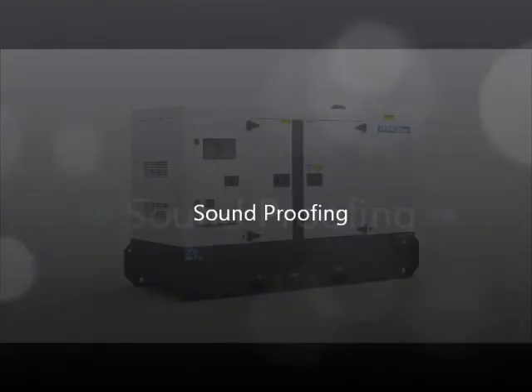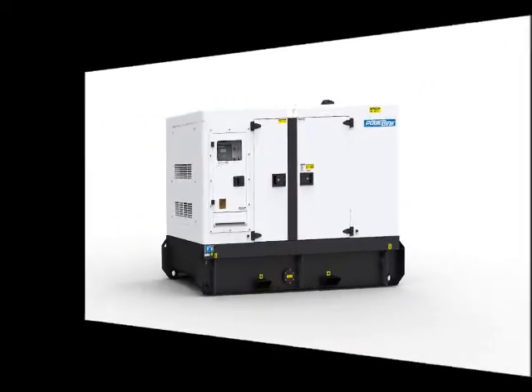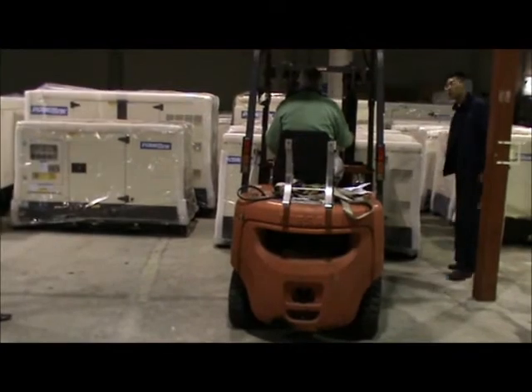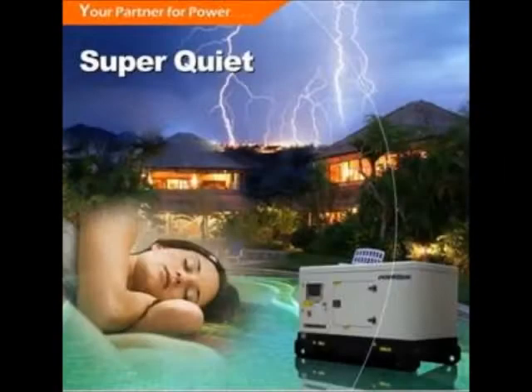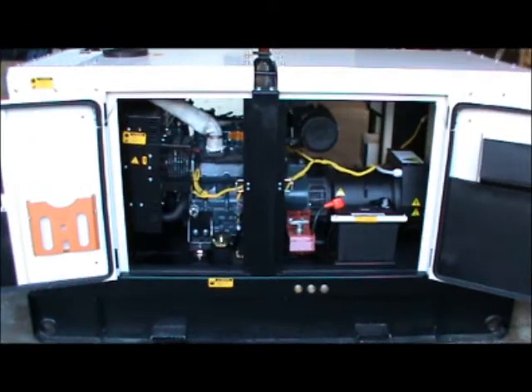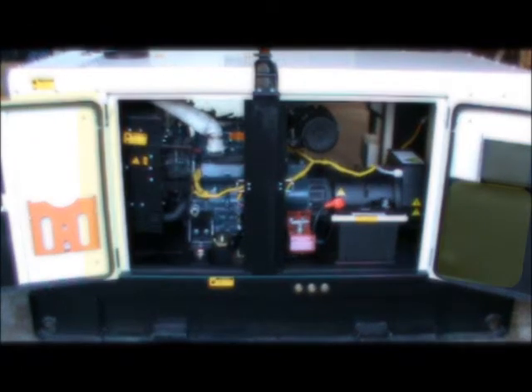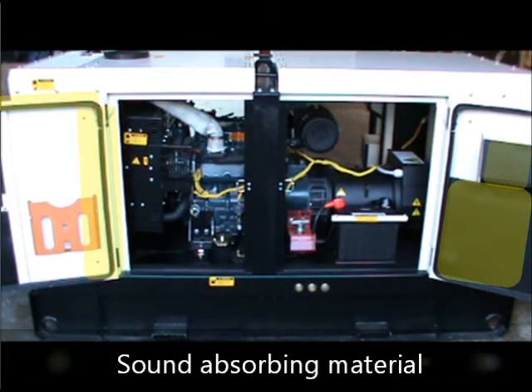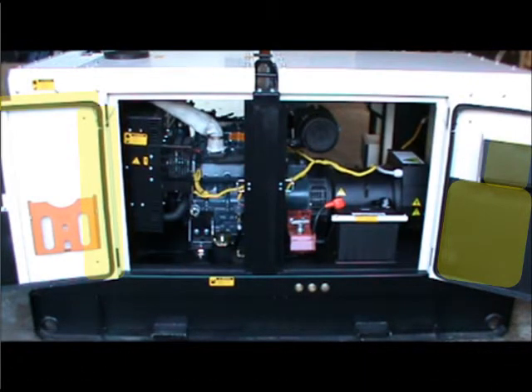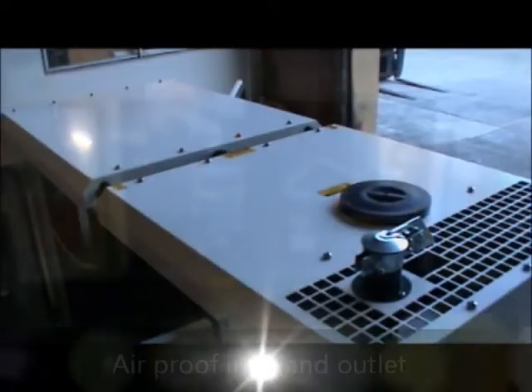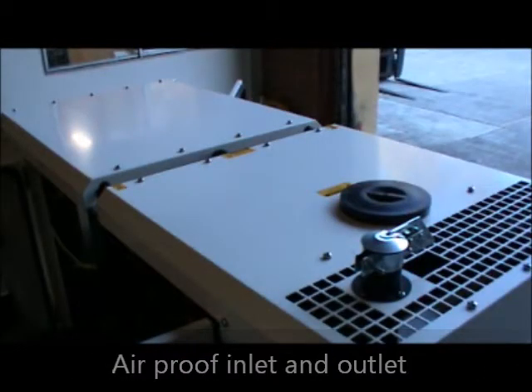service convenience. It is also characterized by its soundproofing quality, with a 67 decibel rating at 7 meters. Most work sites, industrial areas and residential areas have regulations on noise pollution, hence all PowerLink closed set generator sets are designed with the highest level of soundproofing. The interior is lined with fire retardant sound absorbing material, the doors lined with rubber similar to car doors. The inlet and outlet are airproof treated to further lower the noise.